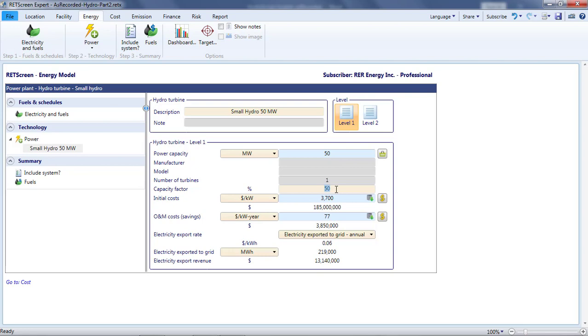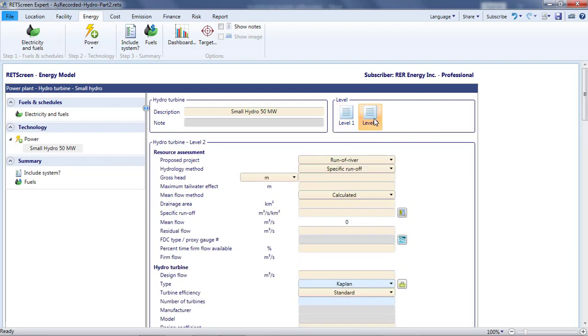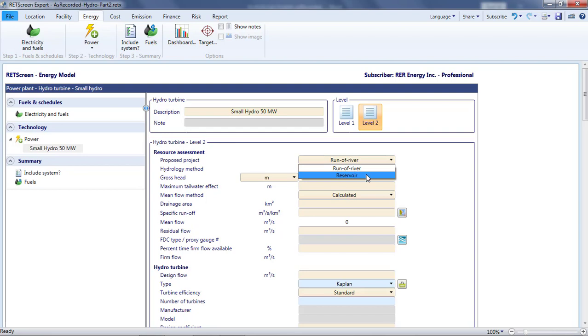On the energy page, I'm no longer satisfied to merely guess at the capacity factor. I want to calculate it based on the flow duration curve and head that I have been given. To do this, I'll change to a level 2 analysis. I indicated earlier that this is a run-of-river project, that is, a project lacking sufficient upstream storage to permit flexibility or choice in the flow used by the turbines. Reservoirs permit flow to be used when it is most advantageous, but tend to have higher civil works costs and environmental impacts. Run-of-river installations make use of the flow at the time it is available, regardless of whether this is when there is a strong demand for electricity. Their costs and environmental impacts are lower, however, and most small hydro projects are run-of-river.